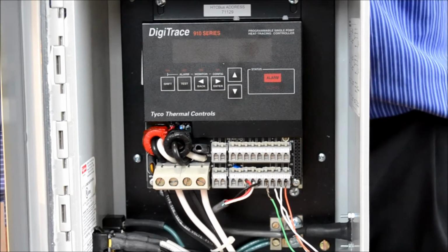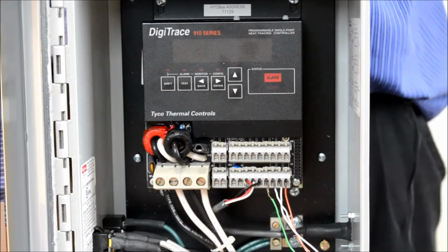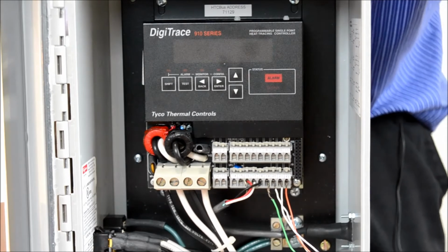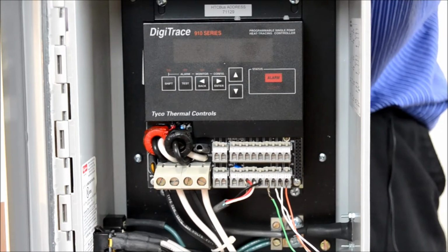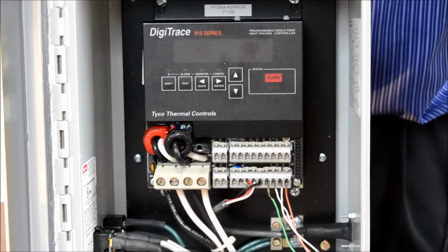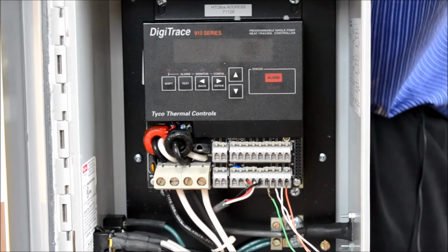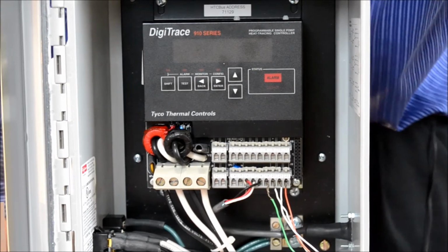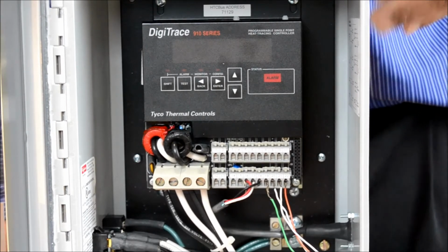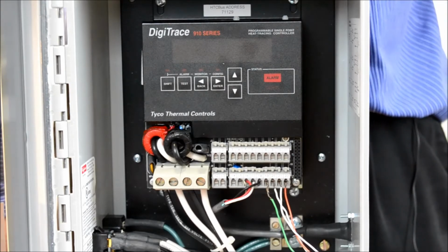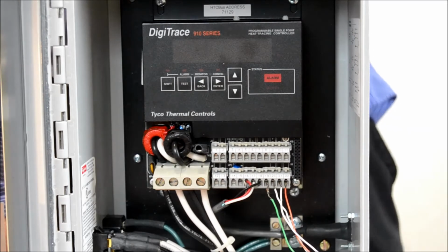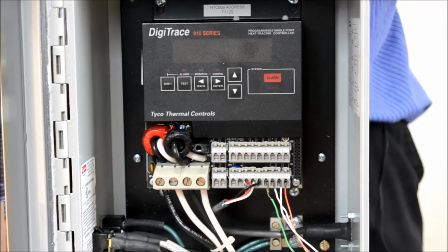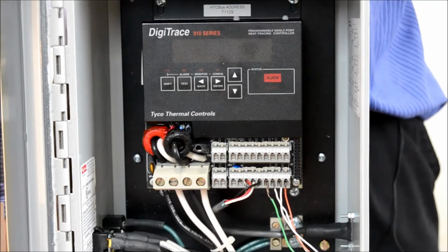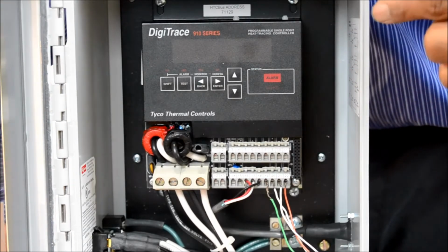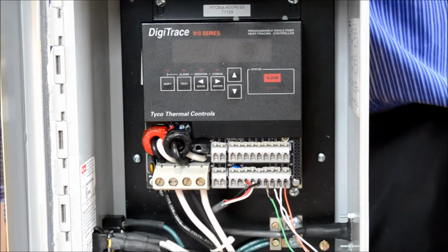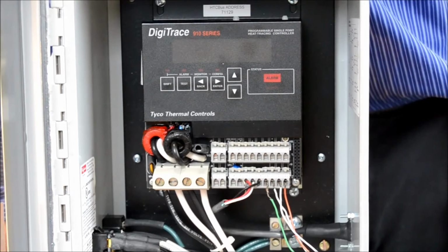Also, this is equipped with ground fault protection. The electrical code mandated back in the 1990s that heat trace must be ground fault protected, and this has equipment ground fault protection up to 30 milliamps. Also, another feature on this particular controller is it's geared for monitoring. It monitors temperature, it monitors voltage, resistance, ground fault, as I said before, and also wattage as well. You have the ability, and I'll show you a little bit later, to change the set points and different functions in the heat trace controller.